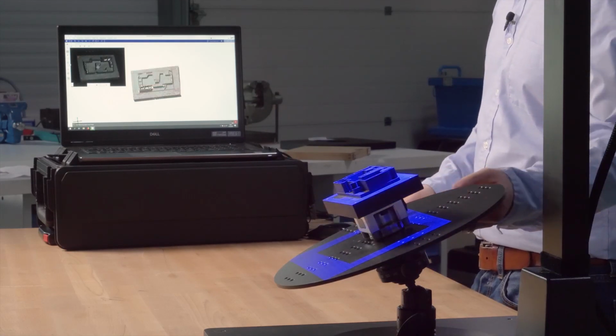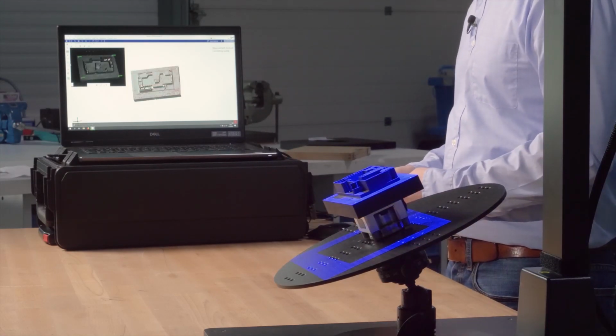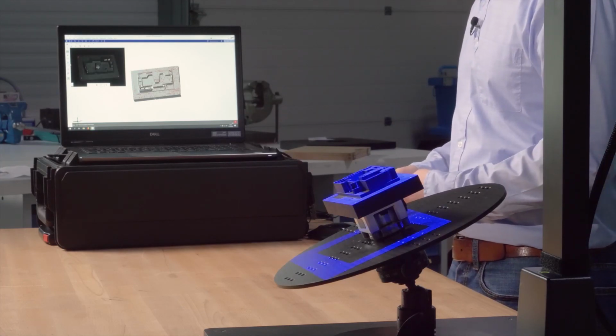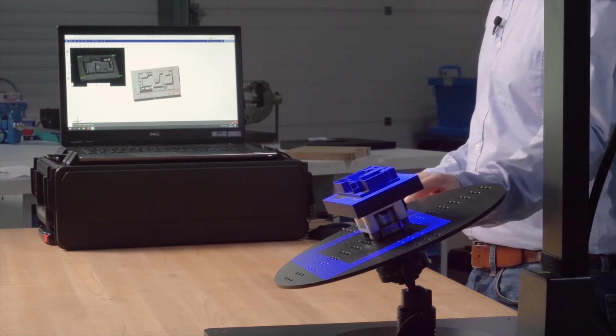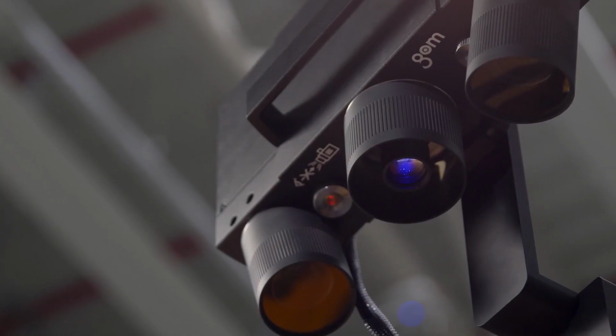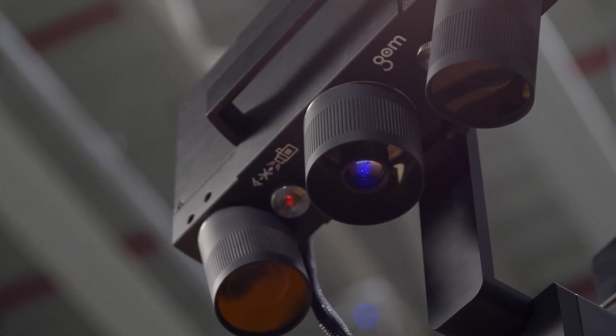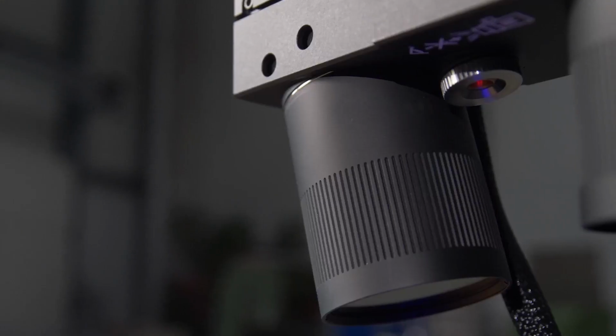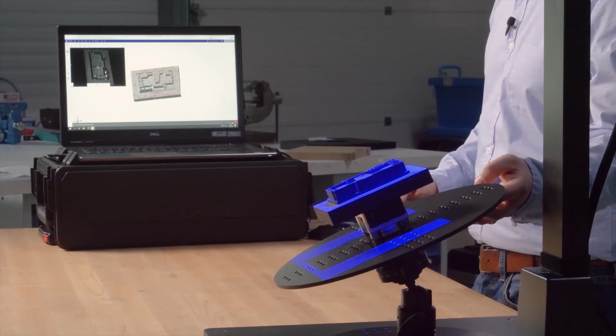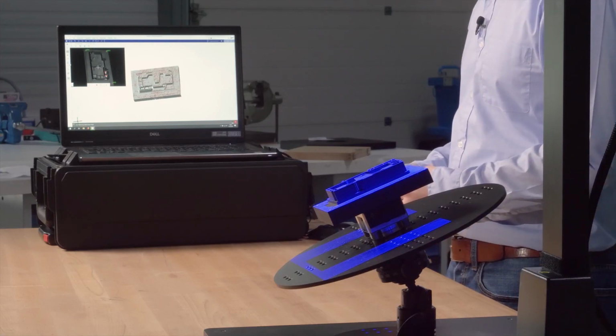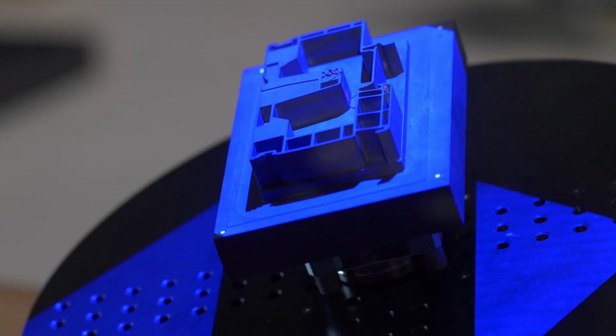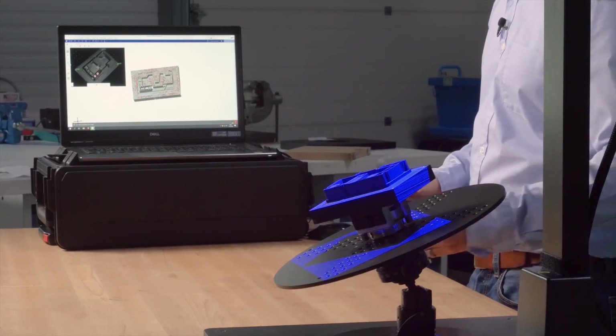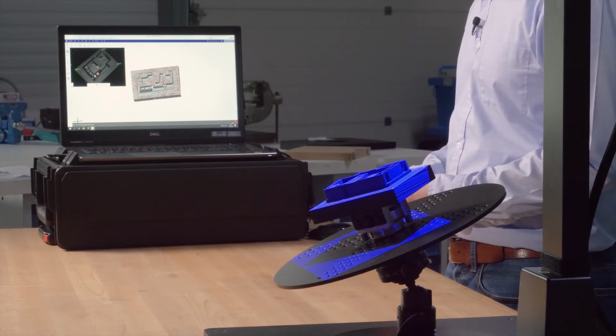The ATOS Q is also taking advantage of GOM's triple scan technology. That means for every sensor position, we're looking at 3 different viewpoints. The first thing the system's going to do is take a look at what it sees from both cameras together. Then it's going to look at the left camera independently and then the right camera independently, so each side can cover what the other one misses. In order to do this, you need to have a precision calibrated 3D camera. The system will automatically combine all 3 different viewpoints for each scan, and this allows us to capture even hard to reach areas easily. So let's take a look now at the data that the ATOS Q got on this part.